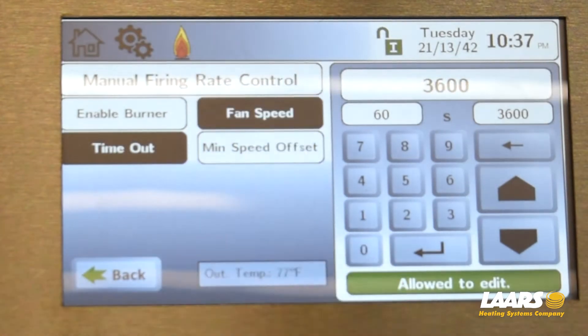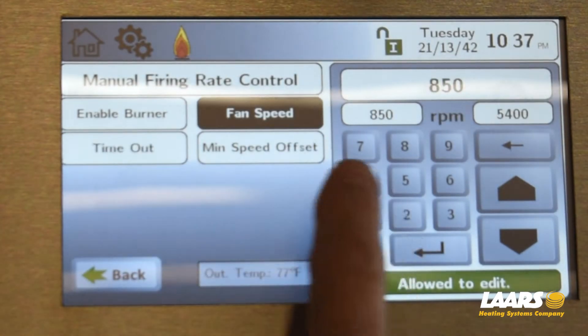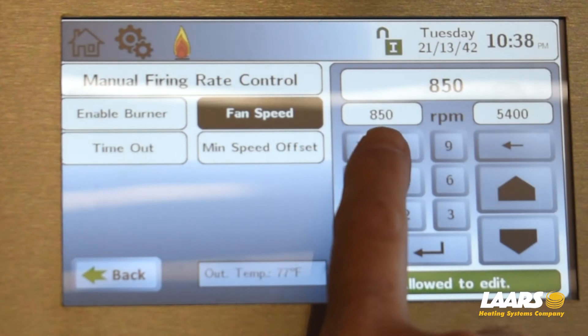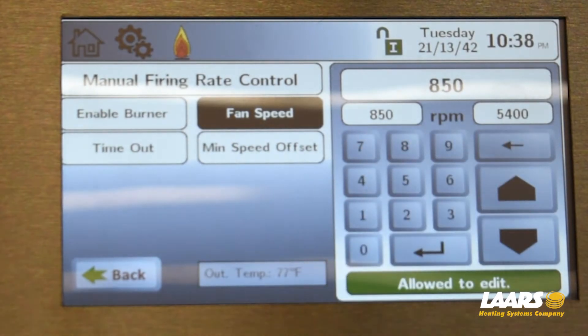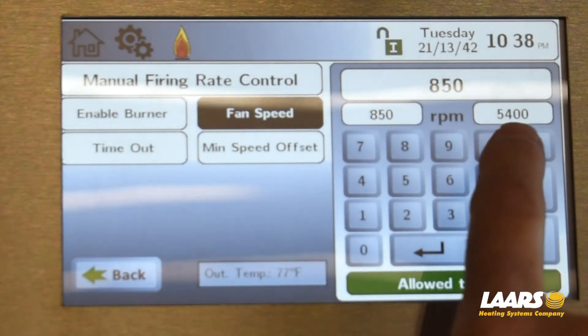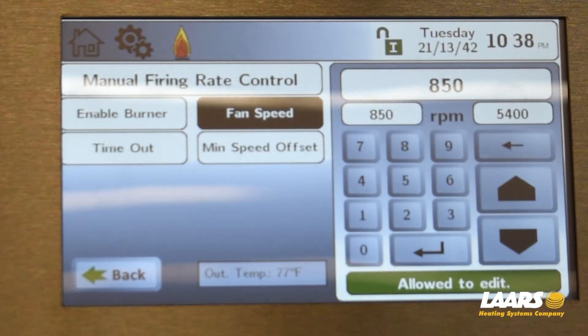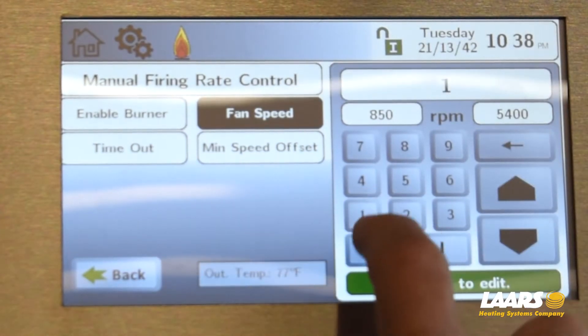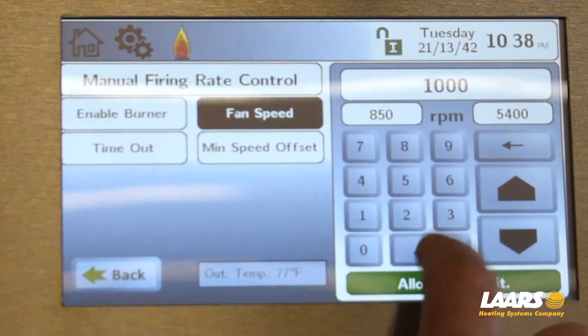Next we'll go to fan speed. Here is our range: 850 RPMs up to 5400 RPMs. High fire or set max will be 5400. For min fire or low fire, we recommend and want to see that at 1000 RPMs. So back that out, type in 1000, and click enter — that will be our low fire.